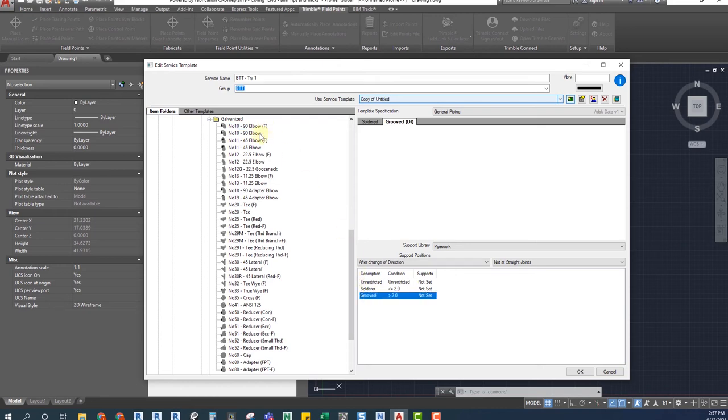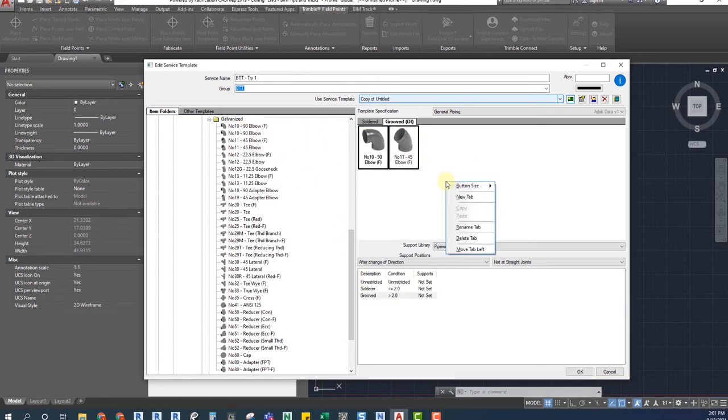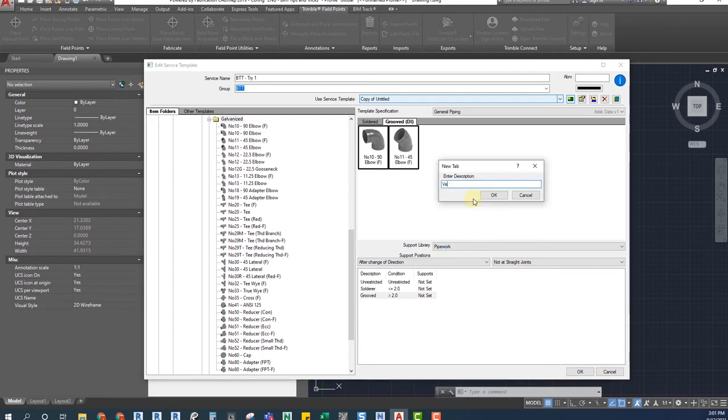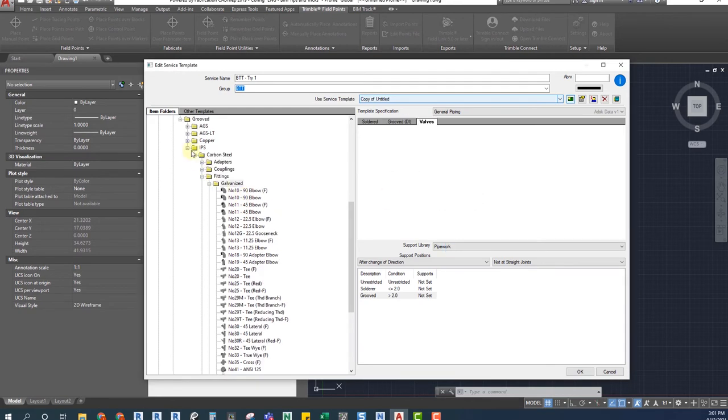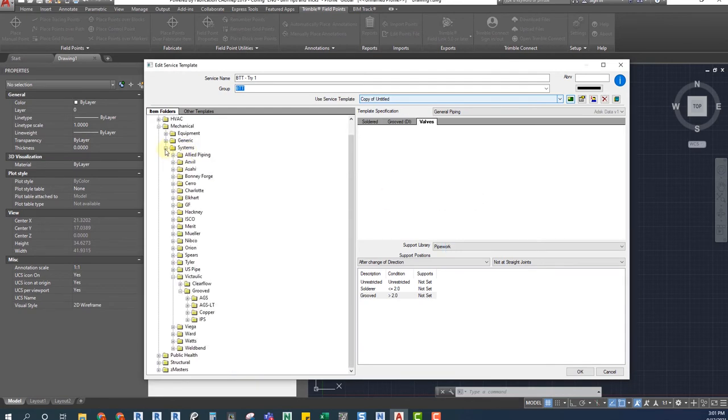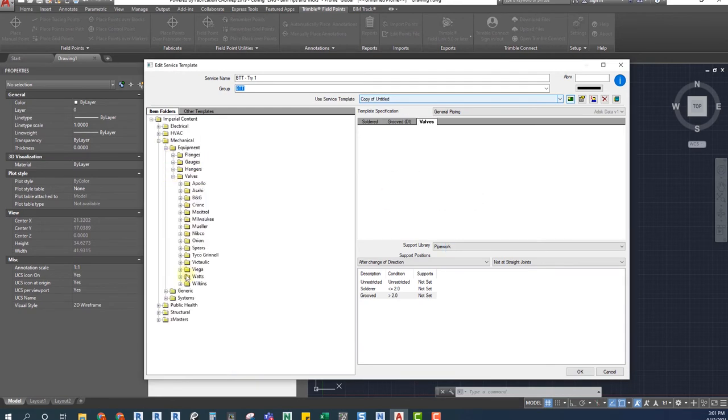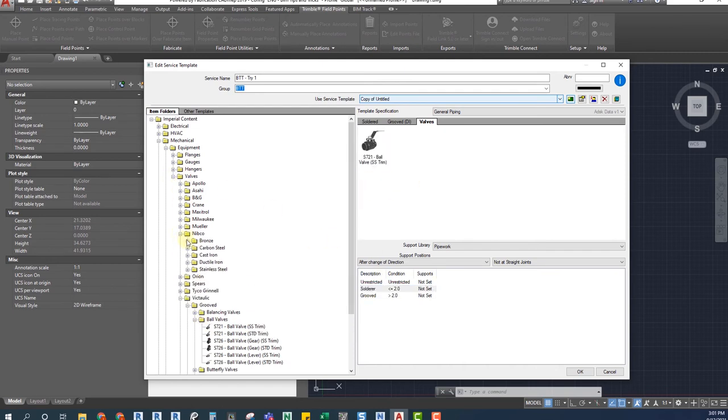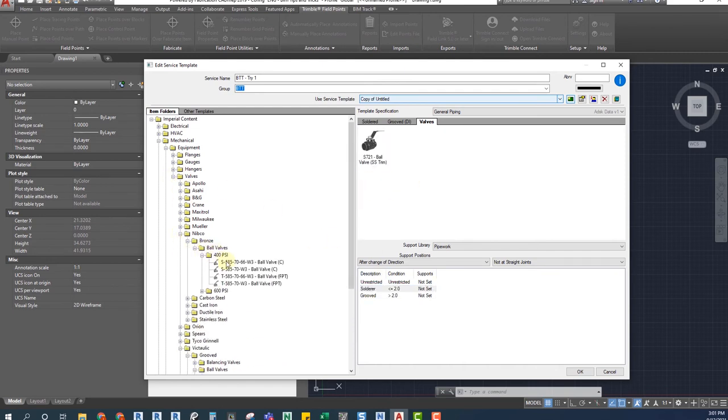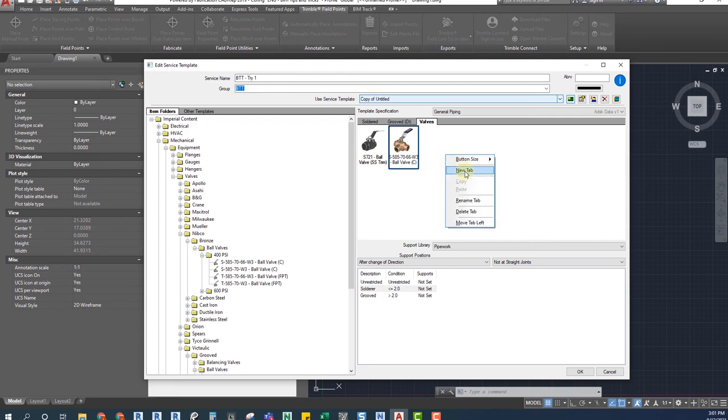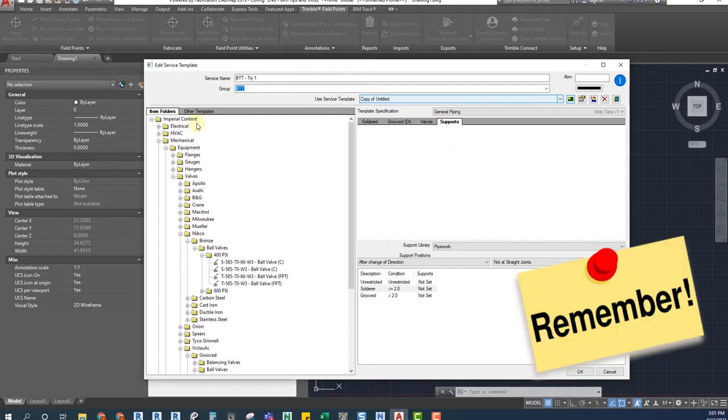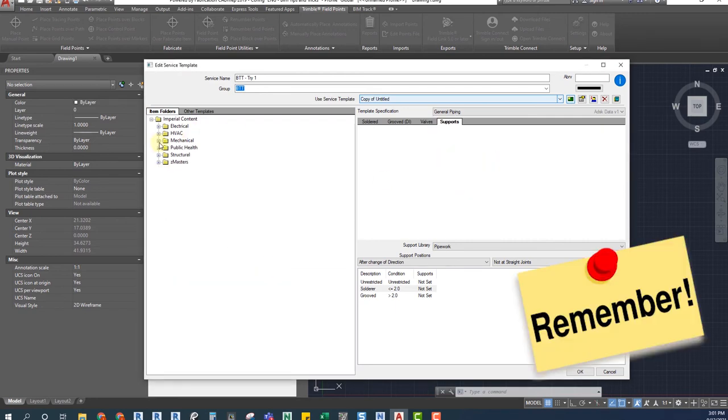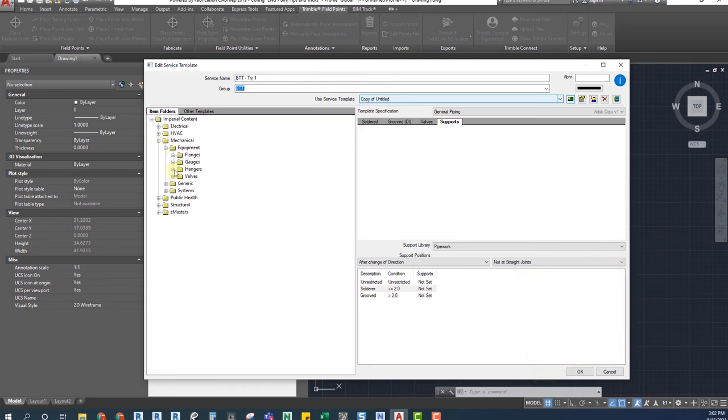The process is pretty similar for adding accessories and hangers since we have to create new tabs as well. To add some valves we will create a new tab and browse into the library for the needed ones. Make sure that the accessory connector matches the pipes connector or you won't be able to place it on Revit. Again, always remember to select the correct sizing conditions. And the same process goes for hangers.